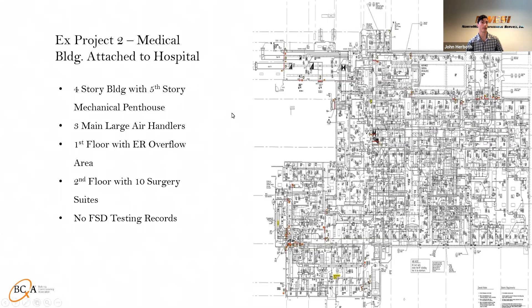So we went through and we had a high rate of failure on this building. 38% failure rate on the FSDs is terrible. Groups of failed FSDs, so that typically points to a relay issue potentially when there's a group of FSDs not working, or a programming issue. And then on top of that, the air handlers didn't shut down.